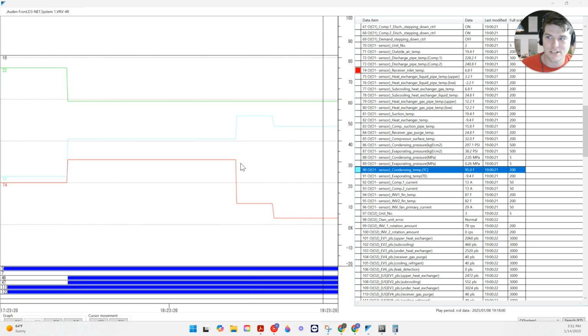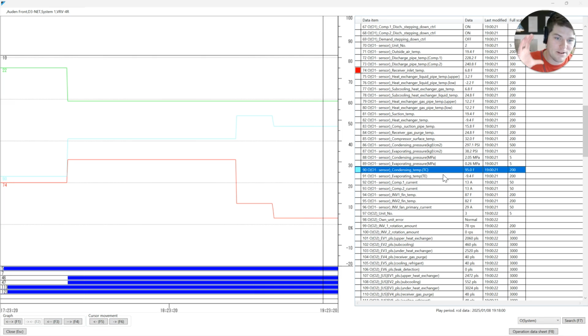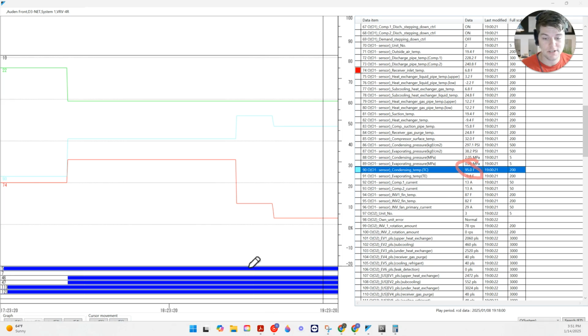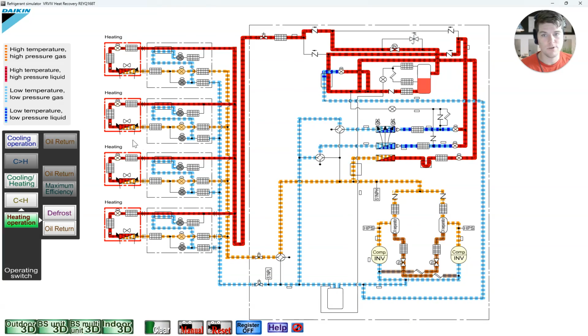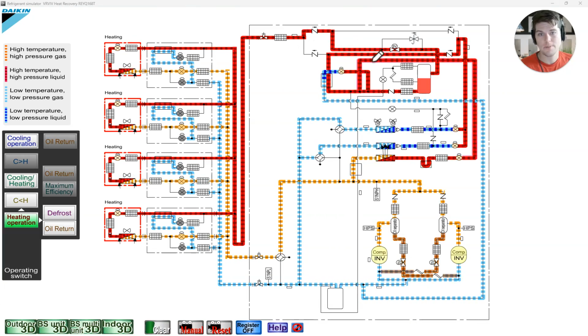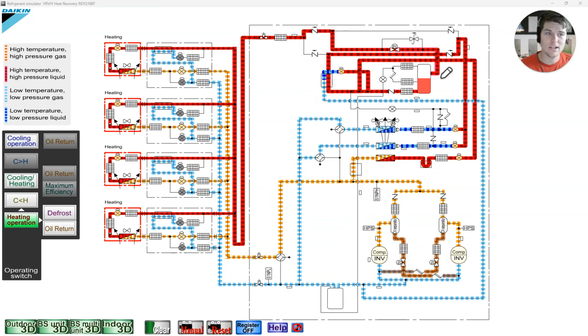So suction temp, condensing temp, liquid temp. What do we know about all these things? They have specific properties at specific states. So we see that it jumps off a cliff. Now we want to know why it jumps off the cliff. And this doesn't make any sense. Why does this not make any sense? Because 6.8 degrees and 95 degrees is a huge difference, which means I have one of two things. I have a large amount of subcooling, or the more possible reason, which I'm going to show you and blow your mind, is this is a low pressure vapor. A low pressure saturated vapor.